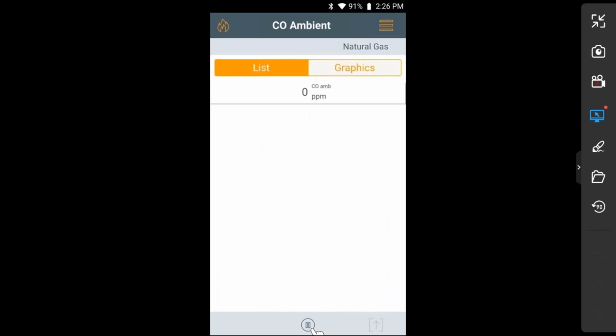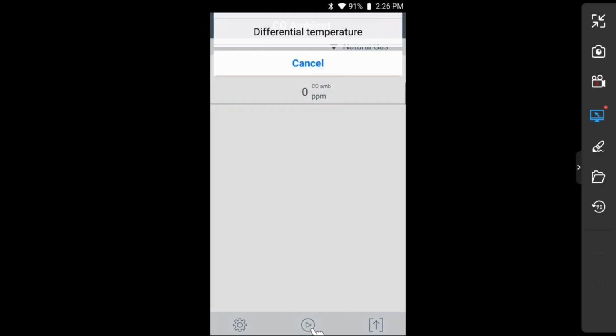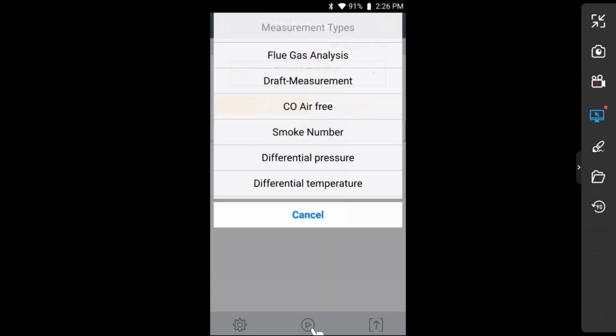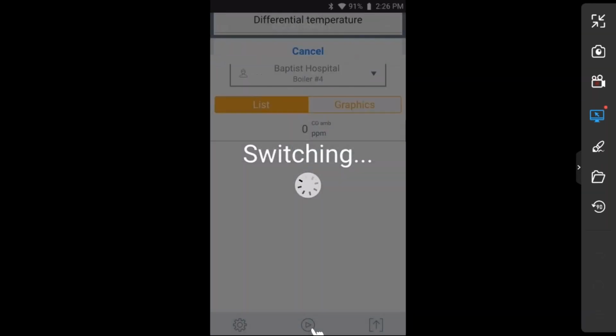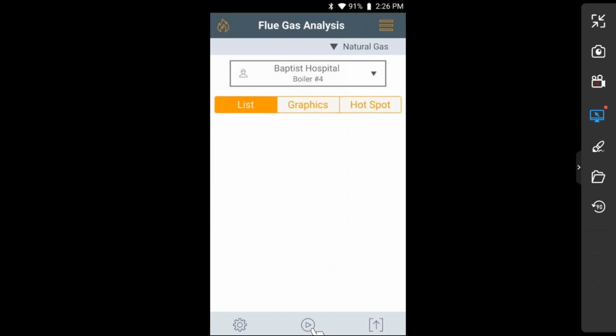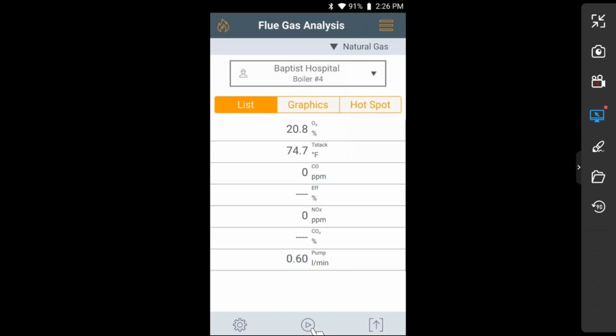Now there are alarms in here as well, so I can set alarms at wherever you like, 10 ppm for ambient air, 20 ppm for ambient air. Stop the pump, go back to my flue gas analysis. This is the screen that you're going to be on the most. This is a screen that allows you to look at many parameters simultaneously.